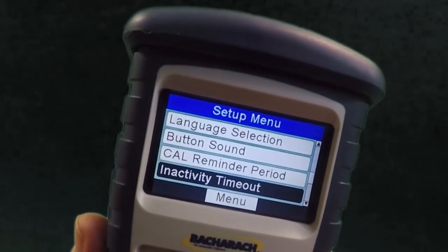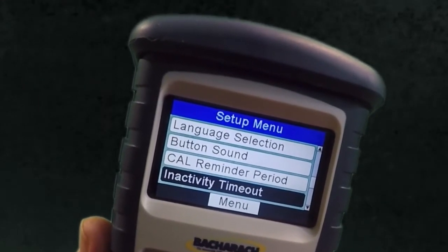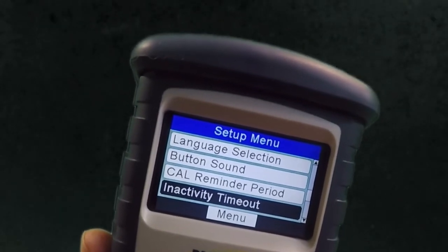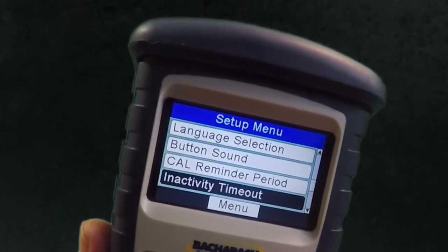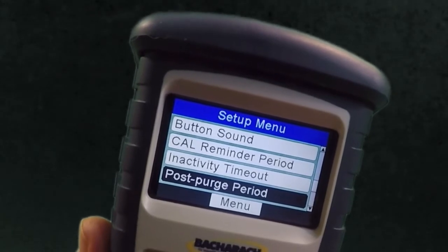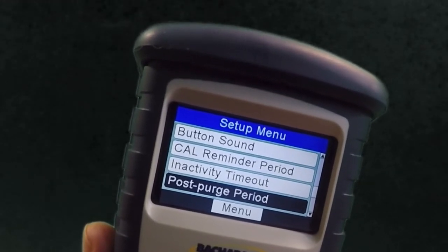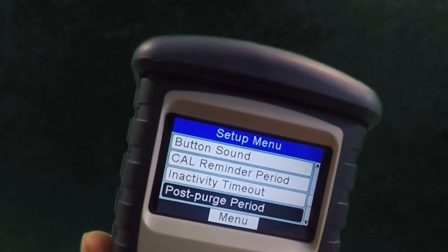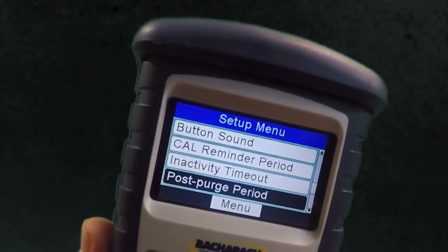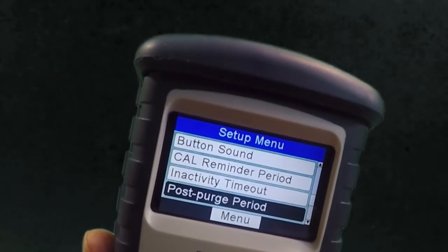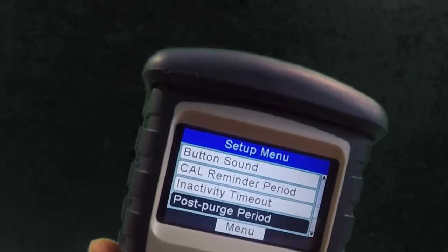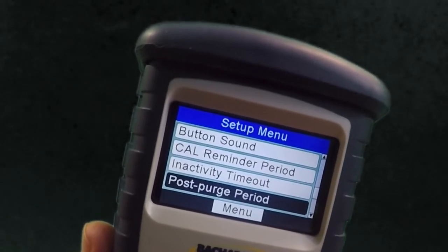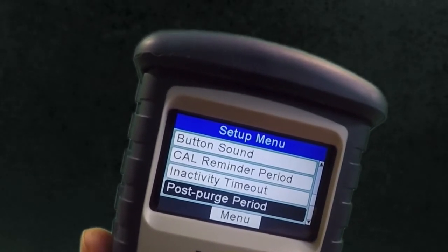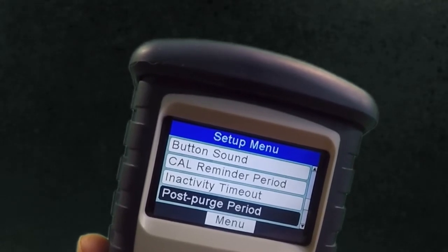Inactivity timeout, that shuts down the instrument if no buttons are pressed during a certain period of time. I'd suggest selecting 20 minutes. Post-purge period, it's a good idea to purge out any remaining flue gases and condensate out of the instrument before shutting it down. I would suggest at least a 1-minute post-purge, or just get in the habit of disconnecting the hose and probe assembly and letting it run for a minute or two before shutting down.